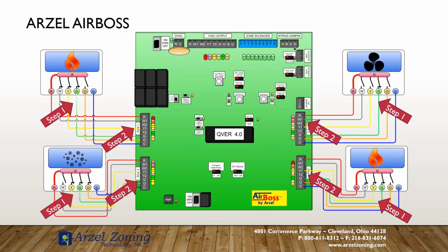If I pull my thermostat head off the wall, do I have voltage between R and W? Do I have it between R and Y, R and G, R and O, R and C? If I have voltage between R and each of those terminals, then I need to make sure that none of my connections, W, Y, G, O, are potentially shorted together. But if those check out good, there are no shorts between W, Y, G, O, and I have voltage between R and each of those wires, then I know my thermostat cable's good. My problem has to be with my thermostat itself.